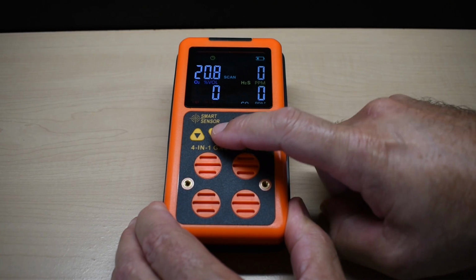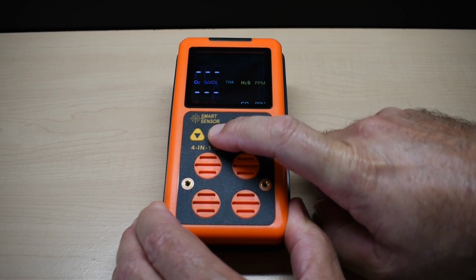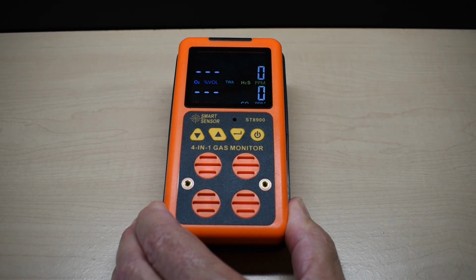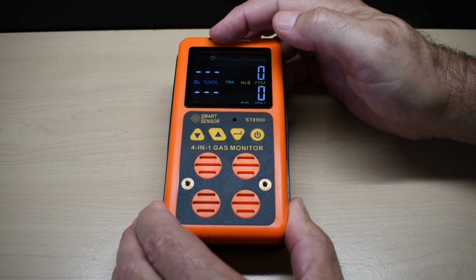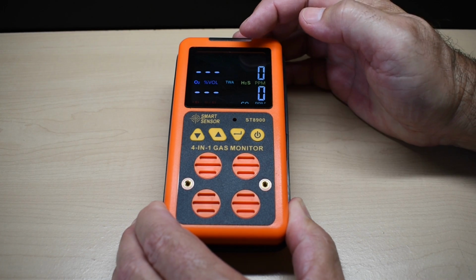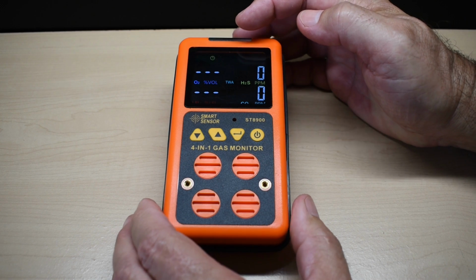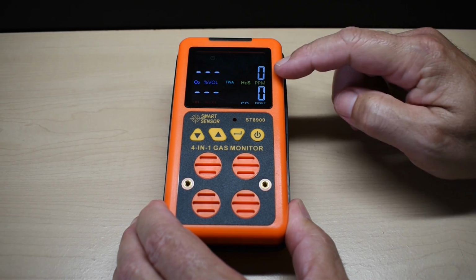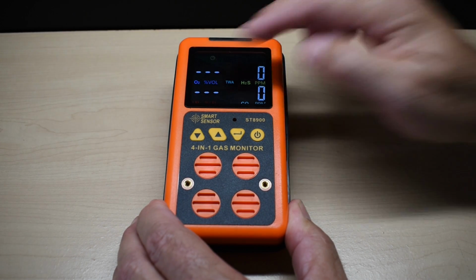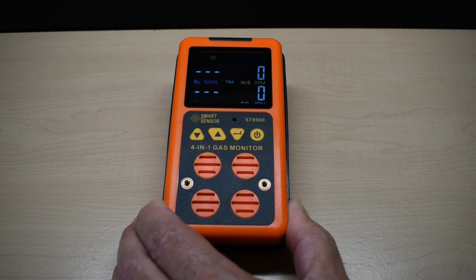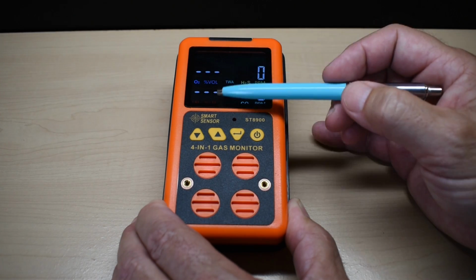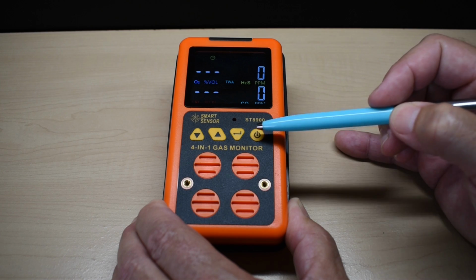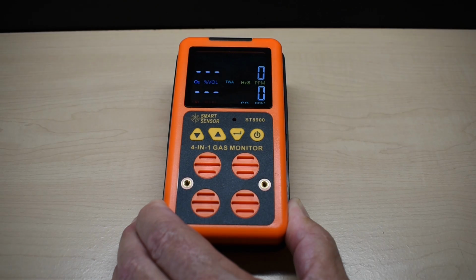So if we push this up arrow again and again, now you're into TWA, and you can see the clock flashing. This is a time-weighted average, so you're going to have an average of only the toxic gases over an 8-hour period. After a day's work, you'll have your averages right here. When you power the unit off, it's going to reset everything.